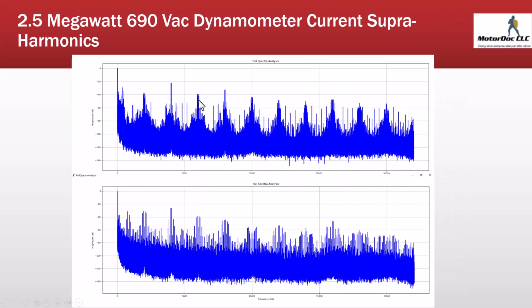Now, the other thing we get to do when I have a higher frequency is something we're talking about these days in the engineering end, standards and utility side, called supra-harmonics. Supra-harmonics are harmonics that occur from 2 kilohertz out to 150 kilohertz. One of the things you get to look at with a current signature analysis, or this particular device, is the ability to see those harmonics out to 22 kilohertz. These peaks that you see every 2 kilohertz all the way out, those are the drive frequencies.